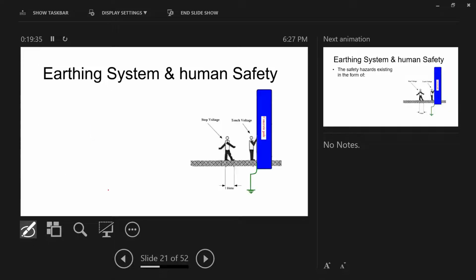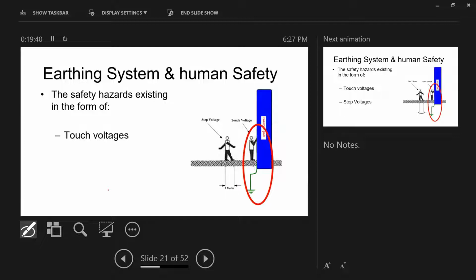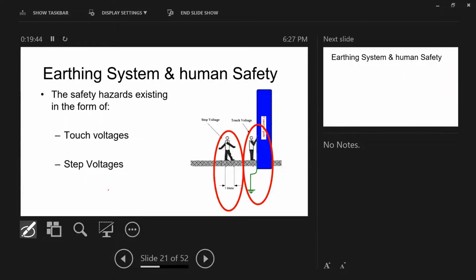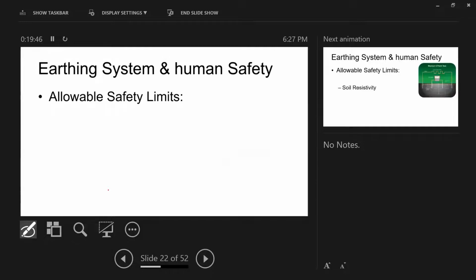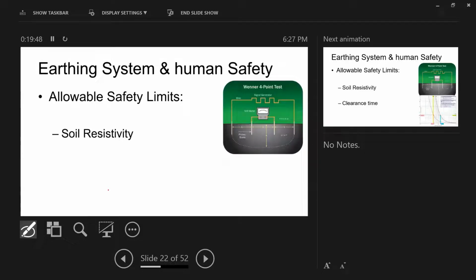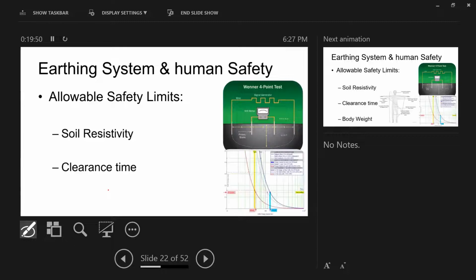You will see more vulnerable. So when it comes to step and touch voltages, I need to define my allowable safety limit. The allowable safety limit depends on two elements: soil resistivity and clearance time. With the American IEEE standard, I need to distinguish between two personnel, a 70 kilogram and a 50 kilogram personnel.